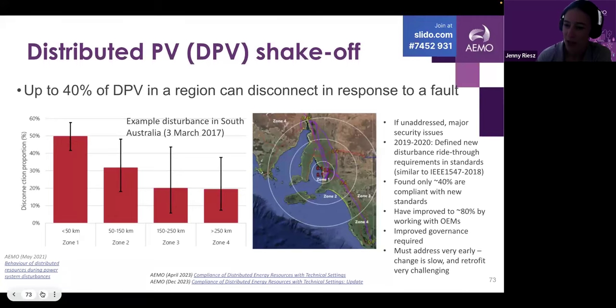So we then were able to get in place our new Australian standard 4777 2020. The challenge since then has been that only about 40% of the new systems being installed appear to be compliant with those new standards, which means that even though the new standard looks to be sufficient to define adequate ride through, they're not being installed correctly on that new standard.